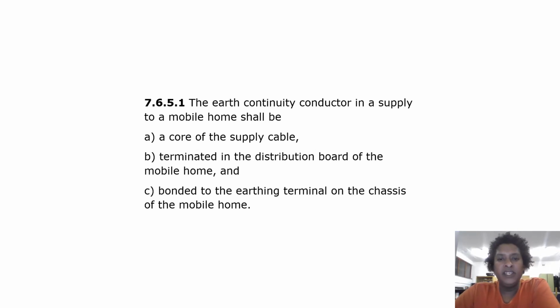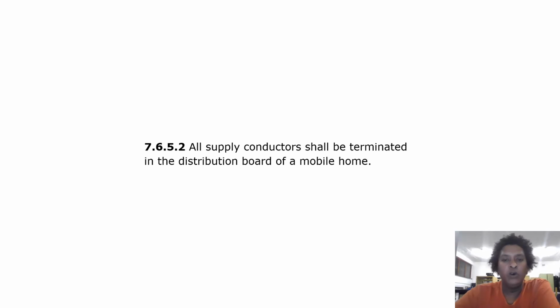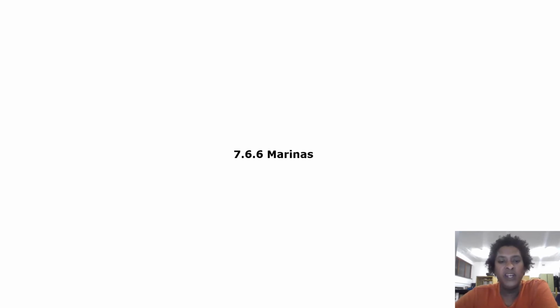Mobile home sites. The earth continuity conductor in a supply to a mobile home shall be a core of the supply cable, terminated in the distribution board of the mobile home, and bonded to the earthing terminal on the chassis of the mobile home. All supply conductors shall be terminated in the distribution board of a mobile home. Marinas.